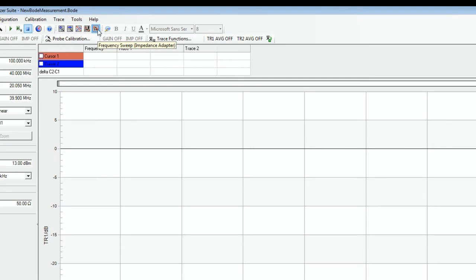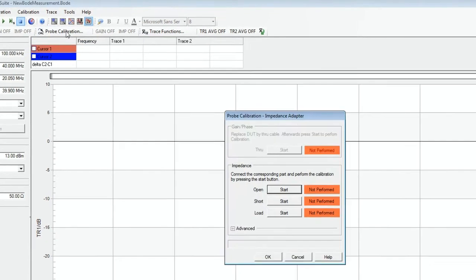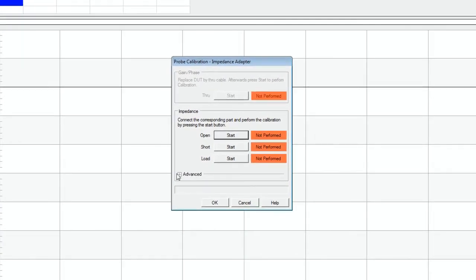Now we are going to perform a probe calibration. For the impedance measurement, we need to do a three-point calibration: open, short and load.